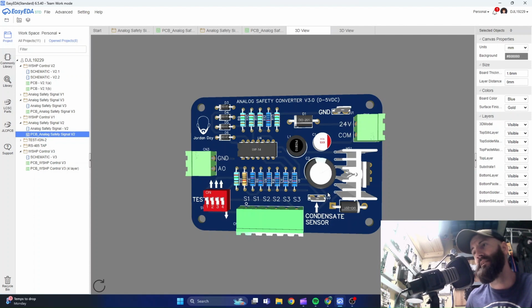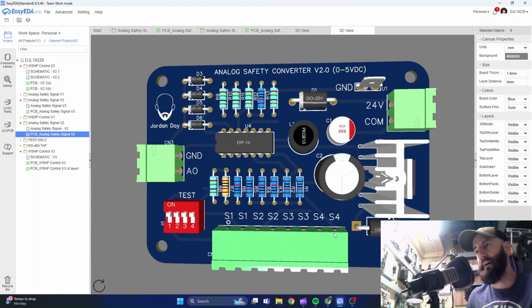Now, what makes this version 3 different from the version 2 is this addition of this condensate sensor. And so we've reduced the safety circuits to 3 normally closed contact safeties, and then of course the condensate safety. Now this is the sensor type. Now you can always use version 2 if you have like a condensate float switch that has a switch built in, but you may be putting this in a device.